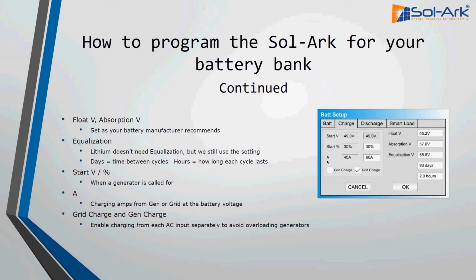Then we have the amp setting here, and this is where you select how many amps to the battery, at the battery's voltage, you want to charge at given the power source. In this case, we have 60 amps if it's coming from the grid, or 40 amps if it's coming from a generator. The reason you can select differently is that a lot of times if you have a smaller generator, you want to make sure that you don't overload it, so you would adjust your charging rate accordingly. And from the grid, a lot of times you'll have that less than the value you would charge from your solar panels, just because why not? It's usually easier on batteries to charge slowly as opposed to super quickly, and you usually have time with the grid.